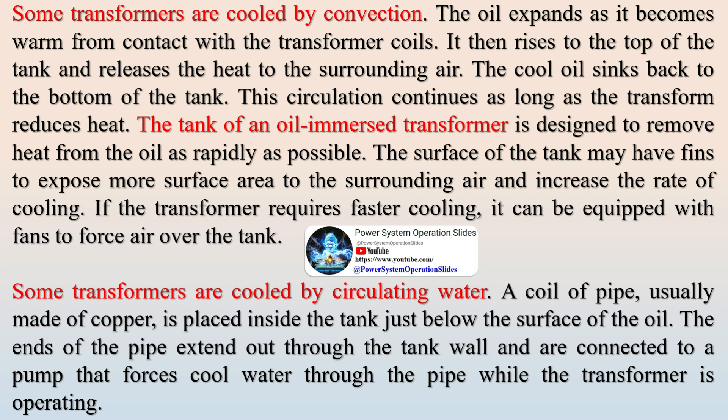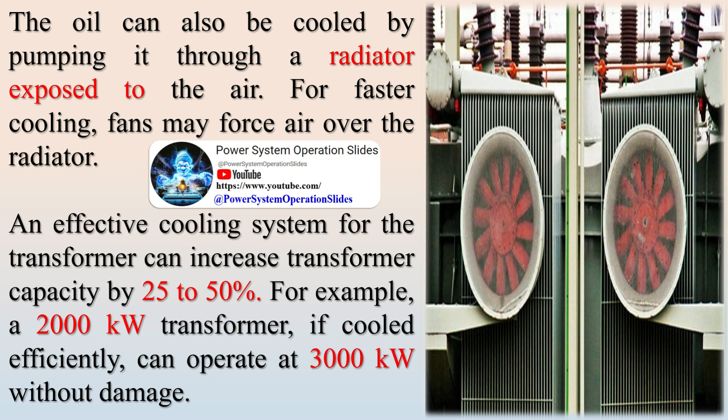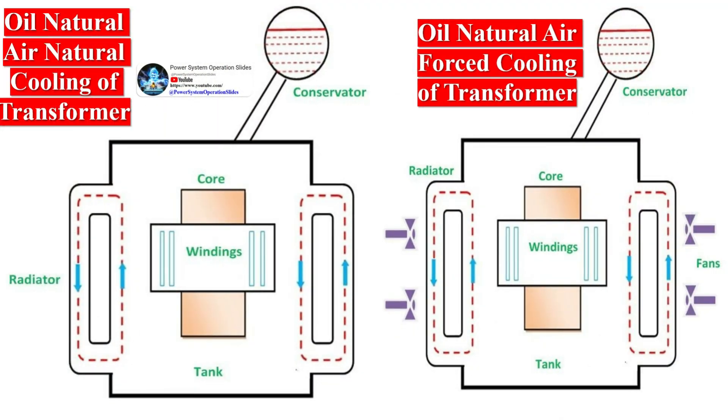Some transformers are cooled by convection. The oil expands as it becomes warm from contact with the transformer coils, rises to the top of the tank, and releases heat to the surrounding air, while cool oil sinks back to the bottom. This circulation continues as long as the transformer produces heat. The tank of an oil immersed transformer is designed to remove heat from the oil as rapidly as possible. The surface of the tank may have fins to expose more surface area to the surrounding air and increase the rate of cooling. If faster cooling is required, the transformer can be equipped with fans to force air over the tank.